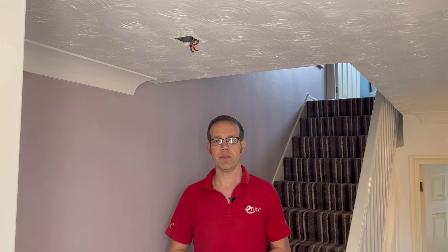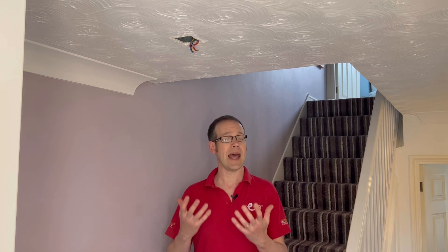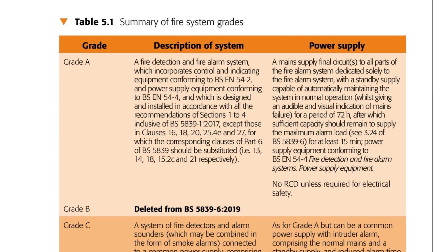The grades are defined by the letters A through F, although there are a couple of letters missing that used to define systems now removed. The technical description of a Grade A system is: a fire detection and fire alarm system which incorporates control and indicating equipment conforming to BS EN 54-2 and power supply equipment conforming to BS EN 54-4, designed and installed in accordance with all the recommendations of sections 1 to 4 inclusive of BS 5839-1 of 2017.